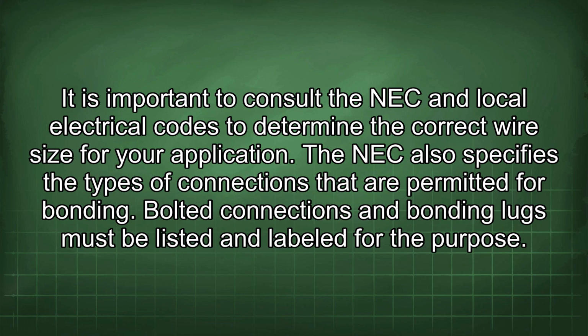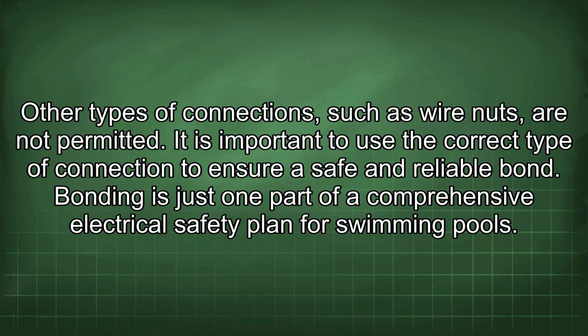The NEC also specifies the types of connections that are permitted for bonding. Bolted connections and bonding lugs must be listed and labeled for the purpose. Other types of connections, such as wire nuts, are not permitted. It is important to use the correct type of connection to ensure a safe and reliable bond.